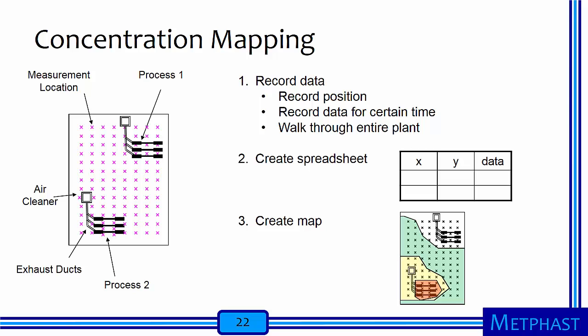In concentration mapping, measurements are made with direct reading instruments throughout a facility. This hypothetical facility has two processes with local exhaust ventilation leading to an air cleaner, which then discharges cleaned air back into the facility. The concentration is measured at each location, noting the X and Y coordinates and the concentration in a spreadsheet. These data are then used to generate a hazard map, where red indicates high concentration and white indicates low concentrations.